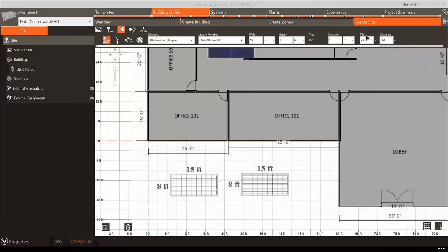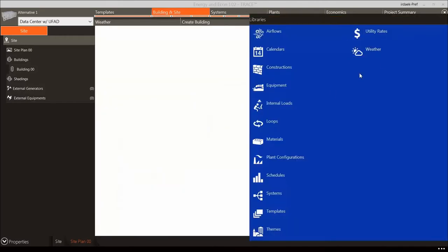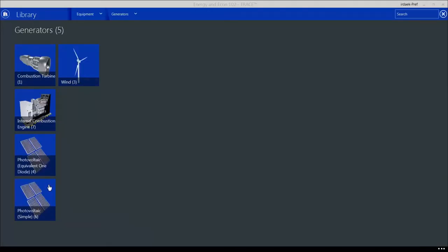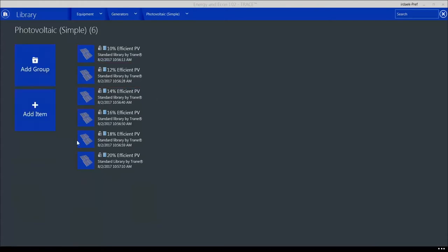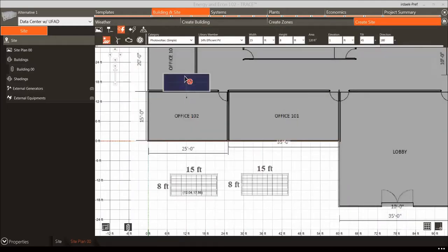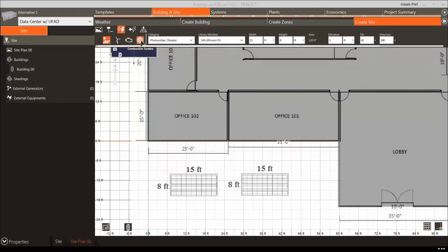Enter 180 degrees for the direction so that they are facing south and double-check the tilt angle is 45 degrees. Use the default library member for the solar panels. In future projects that include photovoltaic arrays, make sure the solar panels have the correct power generation cell efficiency by creating your own PV panels in the Equipment Library under the Generators category. You can also add several other types of generation equipment, such as wind turbines, internal combustion engines, or combustion turbines, the same way as photovoltaic panels.